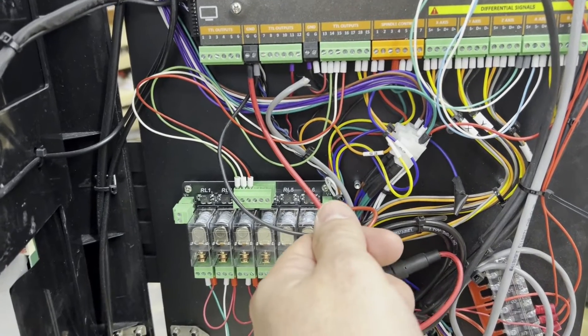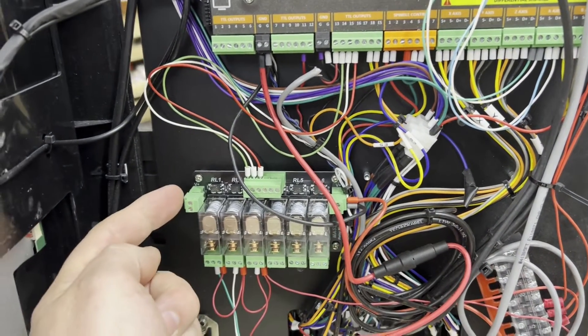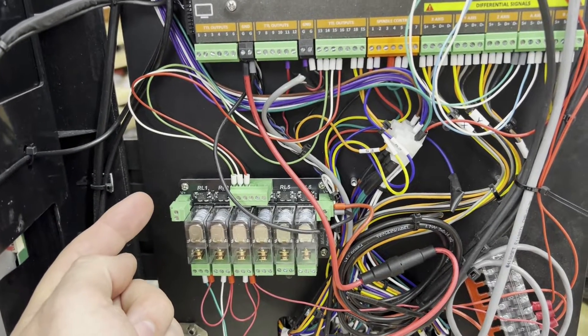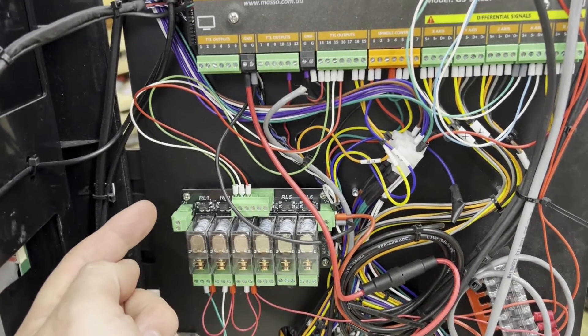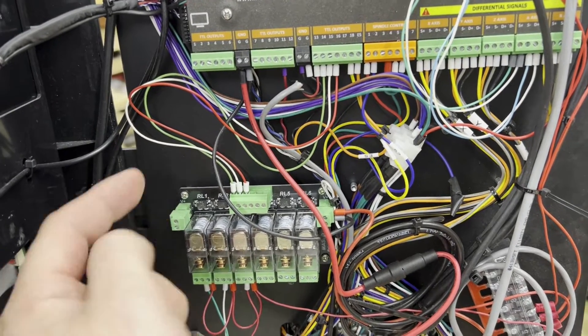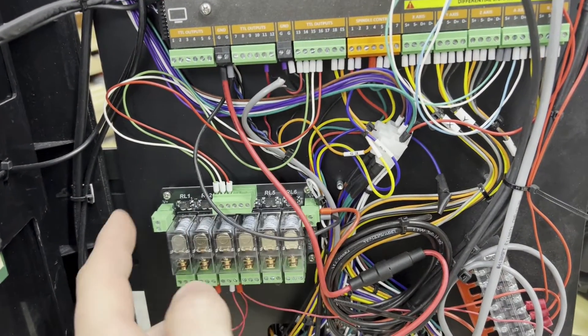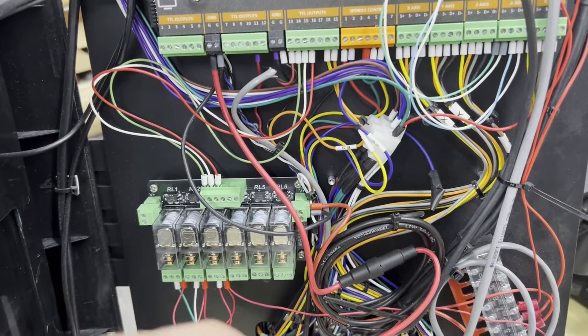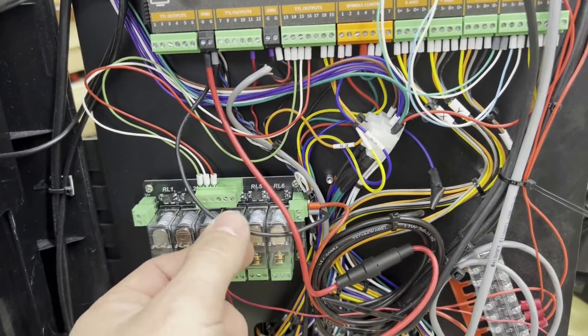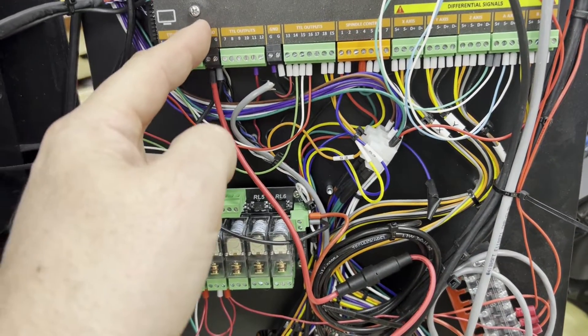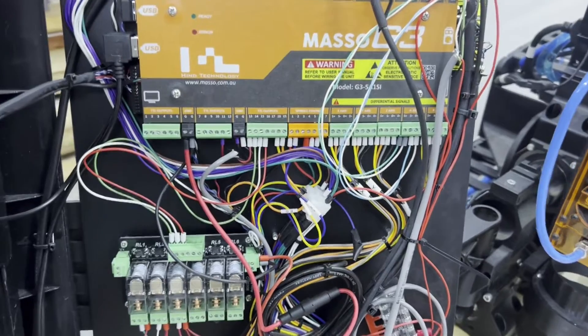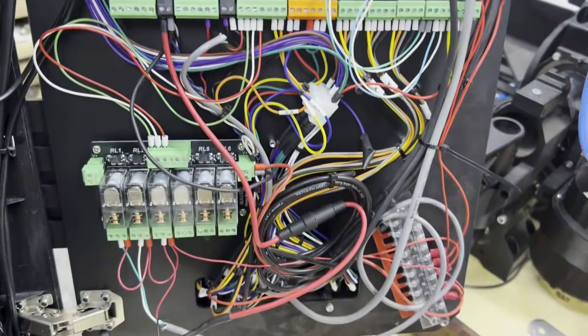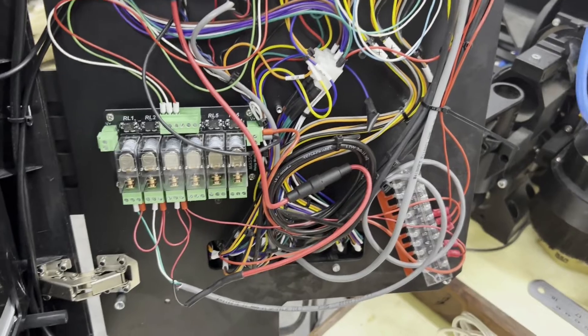So, you've got to be very careful here to make sure your red's always on the top and you're not going to be swapping these back and forth. So that's something very important to pay attention to. So, red's on the top, ground's on the bottom. In my case, I ran the ground back to the MASSO, which is fine to do if you have open ground spots. But it's probably a more scalable solution if you use the terminal block to do that.